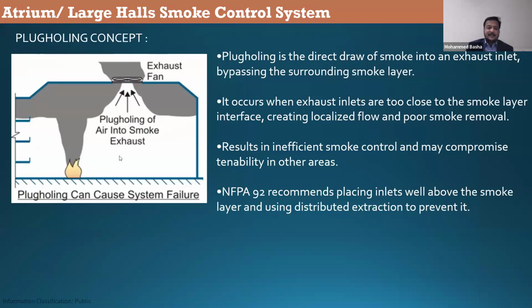Plug holing means a direct draw of smoke into an exhaust inlet, bypassing the surrounding smoke layer. So you can see here, it still extracts, but it doesn't extract properly. It's like a conical space. You are just extracting from one point, which is called plug holing. It occurs when exhausts are too close to the smoke layer interface, creating localized flow and poor smoke removal, resulting in inefficient smoke control and possibly compromising tenability in other areas.